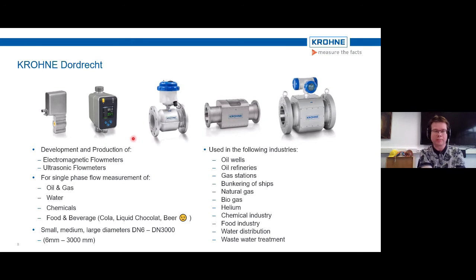So what do we produce? In KROHNE Dordrecht we develop and produce electromagnetic and ultrasonic flow meters, used for single phase flow measurement. Single phase means that through the flow meter you can only measure liquid or gas at one time. The media we measure include oil and gas, water, chemicals, food and beverage like cola, liquid chocolate, or beer—which is my favorite to test when a flow meter is tested with that liquid.